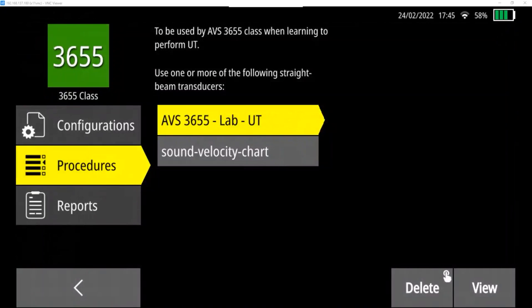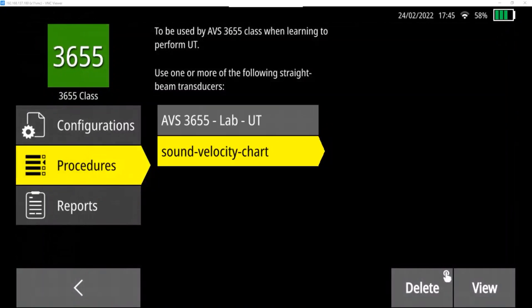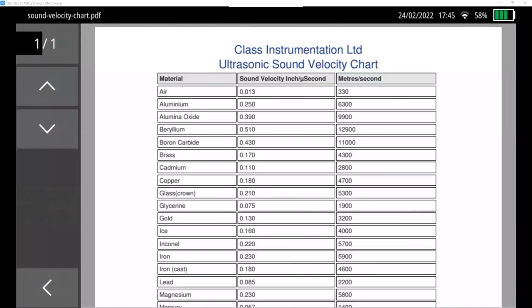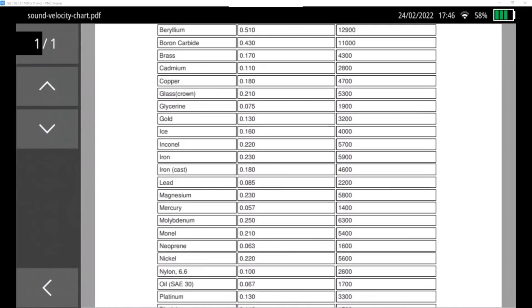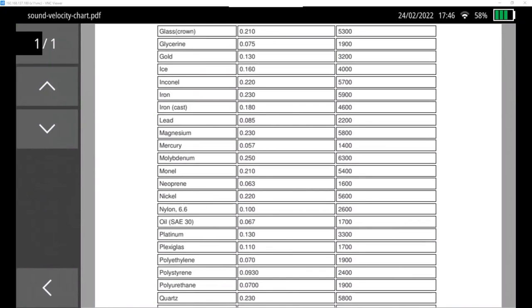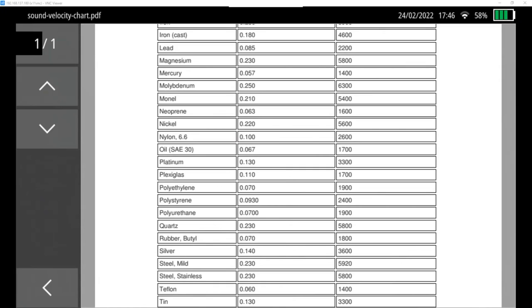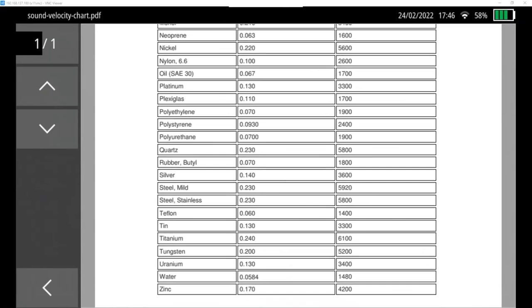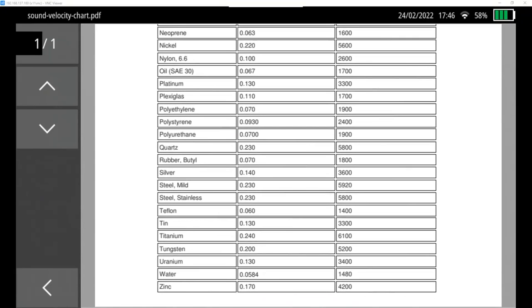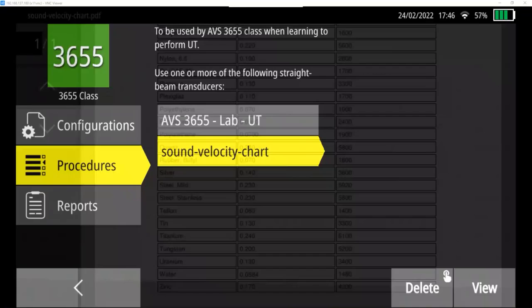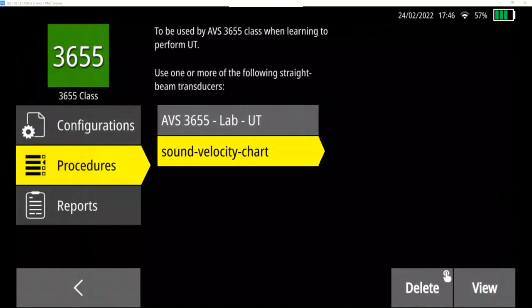There's also a sound velocity chart available on here. Again, by pressing view, it comes up. And so on here we can see aluminum, for instance, is 0.250 inches per microsecond. There's a few other things on here. Iron, 0.230, for instance. Steel is going to be down here near the bottom. Mild and stainless steel, also 0.230. And titanium, 0.240. Those are some of the common materials used in aviation. Hitting the bottom left back button brings you back to this page.